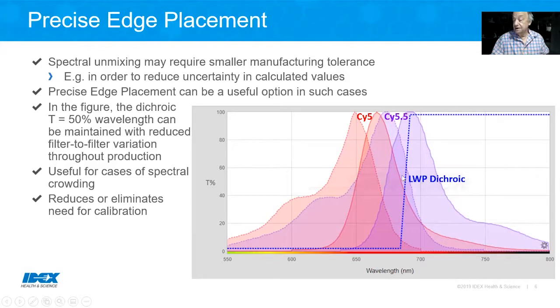The spectral unmixing, however, is confounded to some extent by the manufacturing tolerance inherent in the position of this filter. If the filter moves back and forth from machine to machine, that means there's inevitably going to be machine-to-machine difference. So in this case, we have implemented what we call precise edge placement, in which this edge, the location of this 50% point on the dichroic, is held within better than normal manufacturing tolerance over the duration of the production. So this is a handy capability that could be used in these kinds of cases to, say, eliminate the need for calibration under certain circumstances.